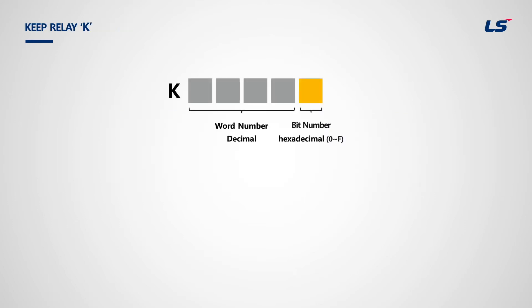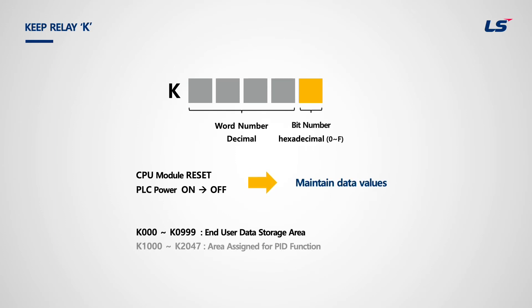Next is keep relay K. It retains data during power failure and can be used without setting a separate retaining parameter. The reset switch in the CPU module will reset all data and clear memory other than keep relay to zero. K memory will hold the last data, and when the CPU is in run mode, it will continue processing with the previous data.